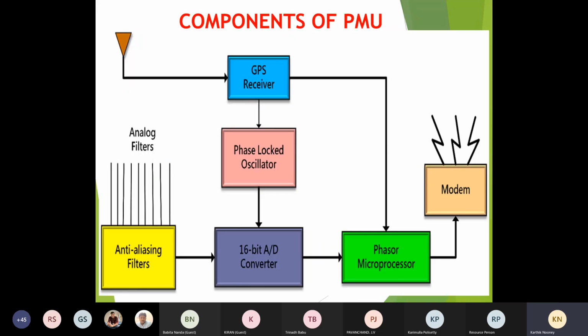This is what the components of PMU are. You have analog filters, anti-aliasing filters, and this data is converted by a 16-bit analog to digital converter, and then a phasor microprocessor is given, where the estimation of these voltages and angles can be done. And this phase locked oscillator is used for the sampling of this particular A to D converter. And GPS has to provide the time synchronization frame. That means exactly at which particular point of time your fault has occurred, and all that analysis of day, year, all the data is given by the synchronized measurements, that is the GPS receiver, and it is connected to the modem for the transfer. And wherever the engineer requires data from other parts also, he can simply access it from the database. This I will explain in the form of a theory here.